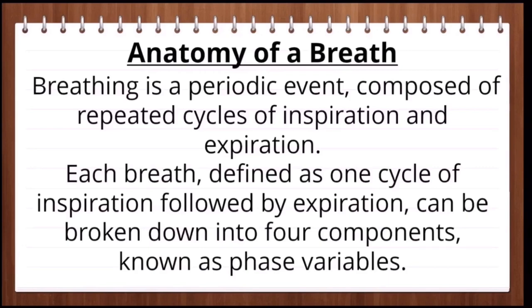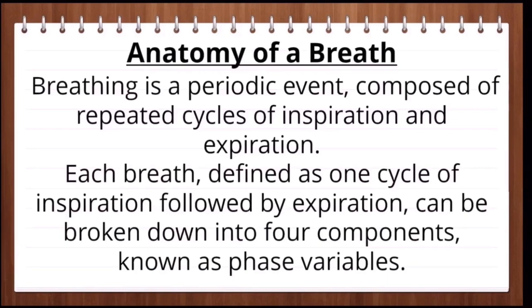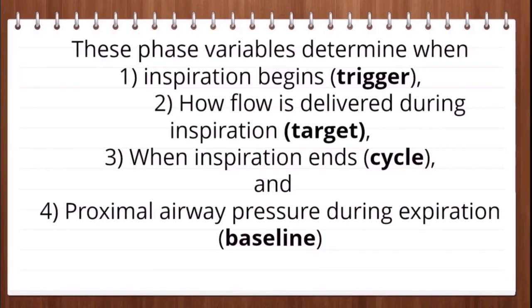Now the anatomy of the breath. Breathing is a periodic event composed of repeated cycles of inspiration and expiration. Each breath is defined as one cycle of inspiration followed by expiration, which can be broken down into four components known as the phase variables. These four phase variables are: first, trigger; second, target; third, cycle; and fourth, the proximal airway pressure during expiration, which is known as the baseline.